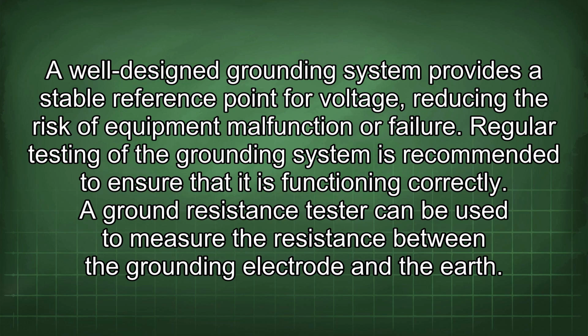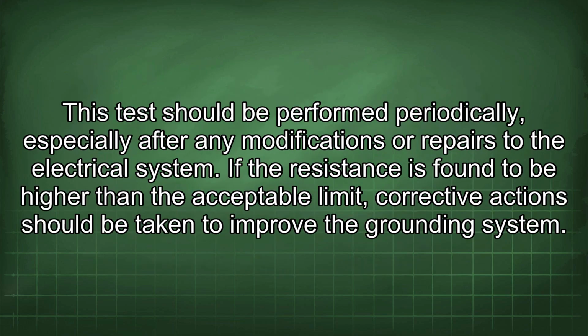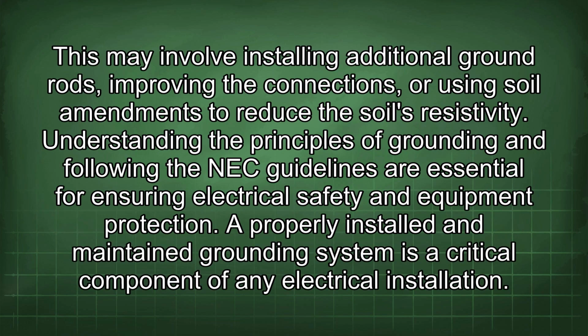A ground resistance tester can be used to measure the resistance between the grounding electrode and the earth. This test should be performed periodically, especially after any modifications or repairs to the electrical system. If the resistance is found to be higher than the acceptable limit, corrective action should be taken to improve the grounding system. This may involve installing additional ground rods, improving the connections, or using soil amendments to reduce the soil's resistivity. Understanding the principles of grounding and following the NEC guidelines are essential for ensuring electrical safety and equipment protection.